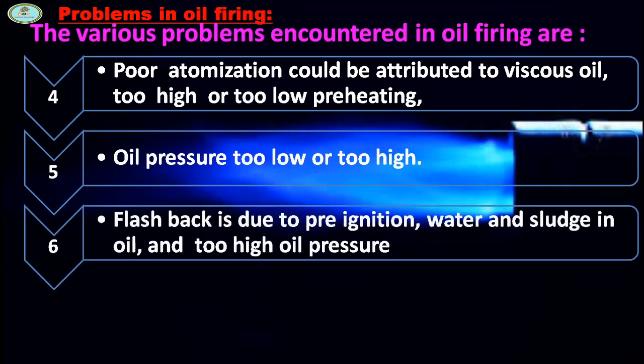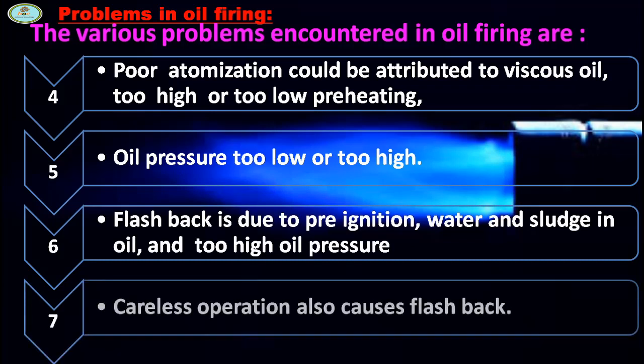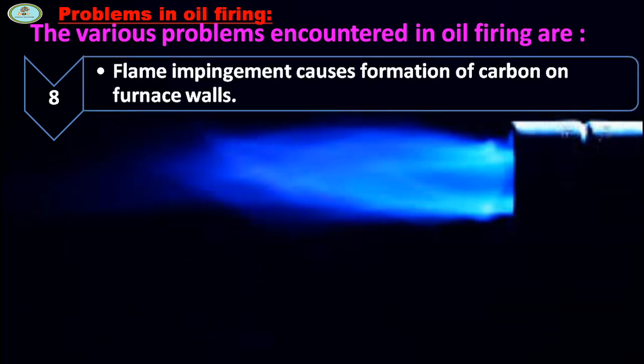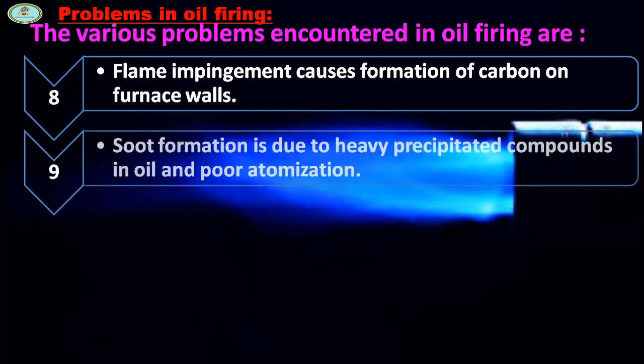Flashback is due to pre-ignition, water and sludge in oil, and too high oil pressure. Careless operation also causes flashback. Flame impingement causes formation of carbon on furnace walls. Soot formation is due to heavy precipitated compounds in oil and poor atomization.